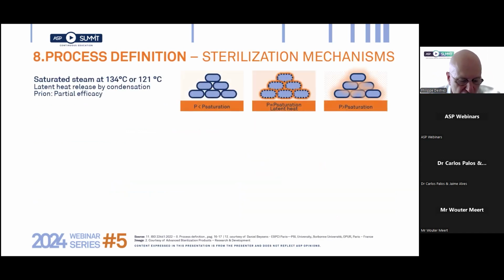So process definition is by law under the responsibility of the medical device manufacturers. Tests must be performed to check that conditions for sterility are consistently achieved with a cycle specified in the instruction for reprocessing. Sterility testing means placing a 6-log spore inoculum at the most challenging location within the device and checking that full inactivation of the spores is systematically obtained. Tests are performed at half cycle to reach the sterility assurance level of 10 to the minus 6 at the end of a full cycle. We will see that on a future slide.